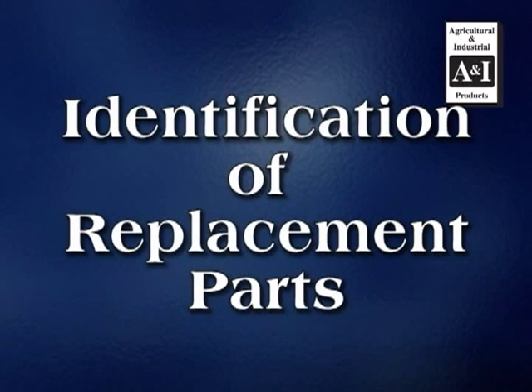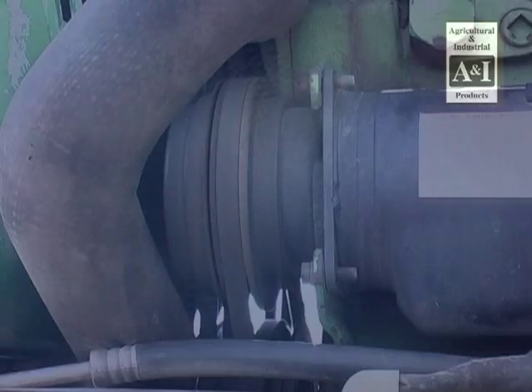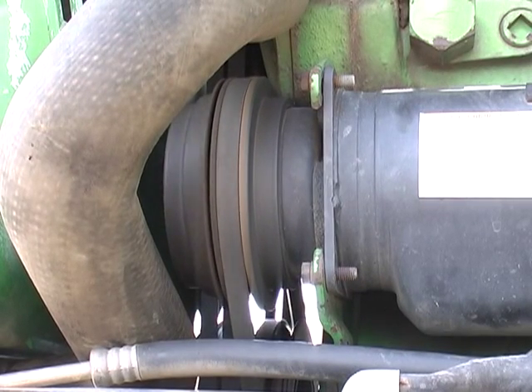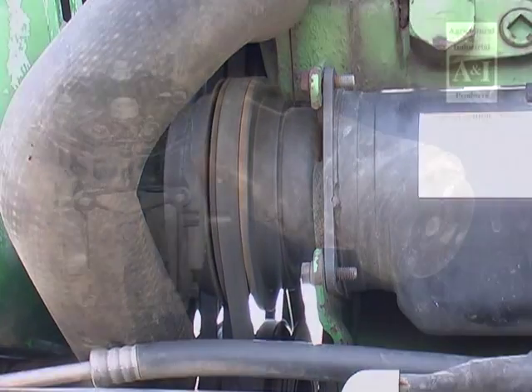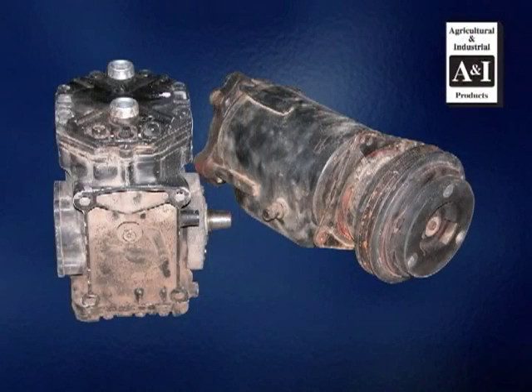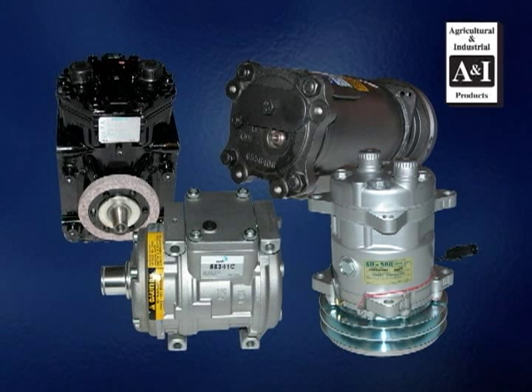Identification of replacement parts. If any leaks are found on the compressor due to compressor vibration, whether it's the shaft seal or housing leaking, the compressor should be replaced. If you discover the compressor is bad, you need to be able to identify it in order to get the proper replacement. There are a variety of compressors used in the ag industry. Proper identification is very important.